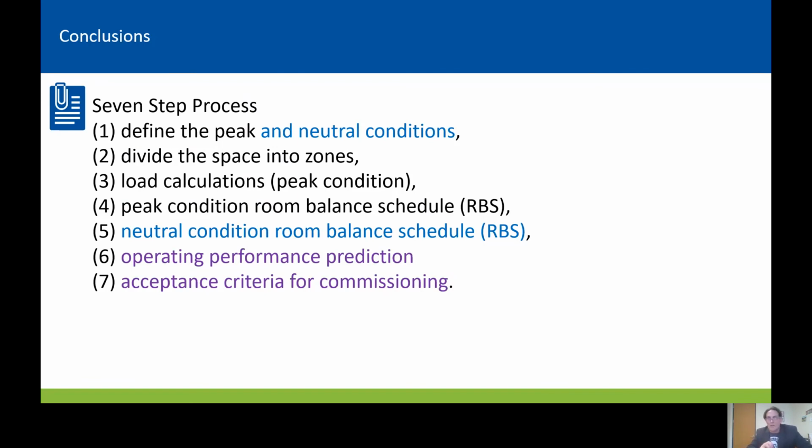I've said before that if we were to leave the lights running in all the office spaces overnight, then we would all be shot or laughed at the very least. But it's extremely common for hospital design engineers to run the HVAC systems at full blast in admin spaces and clinical spaces. You just run it all night, all the time. And so we have to stop that practice. And that's the biggest gap that we see right now, the design engineering community actually designing to and achieving those levels of turndown.